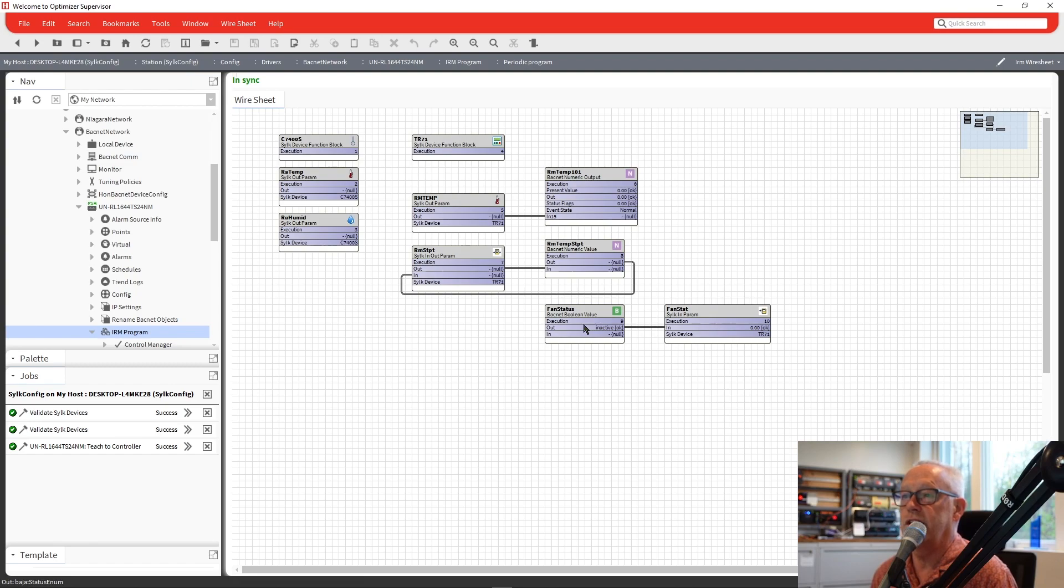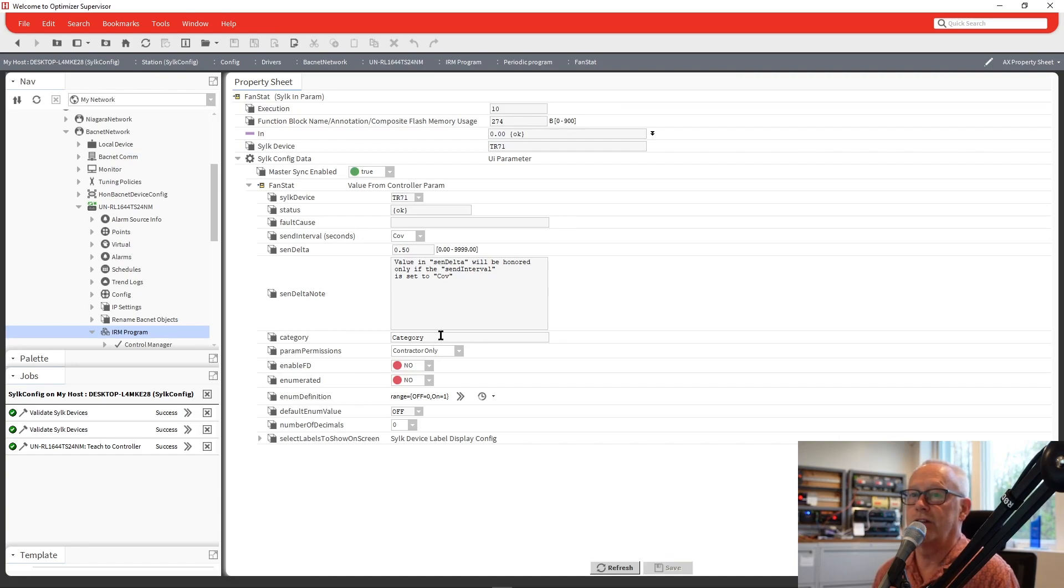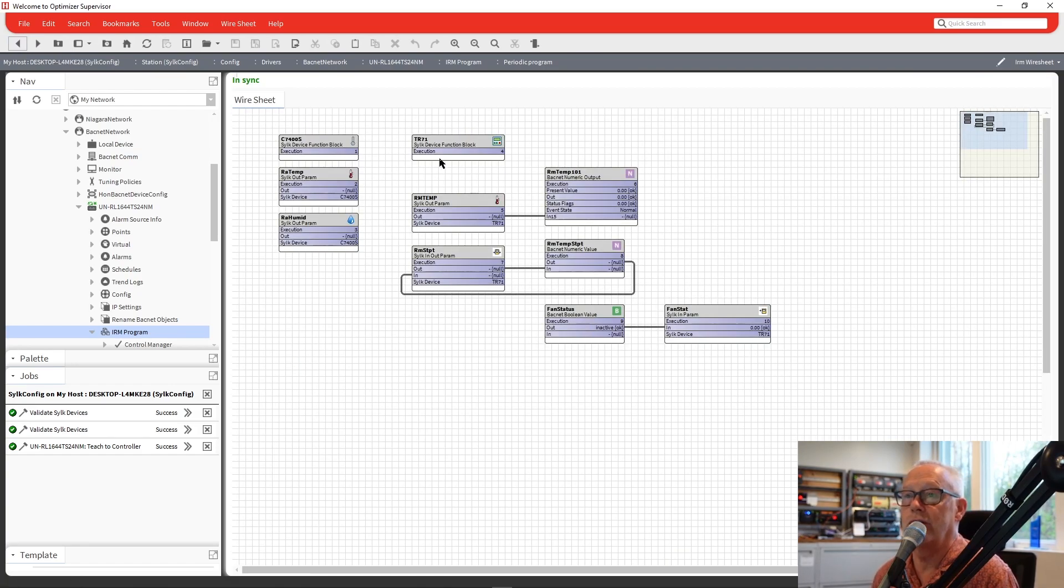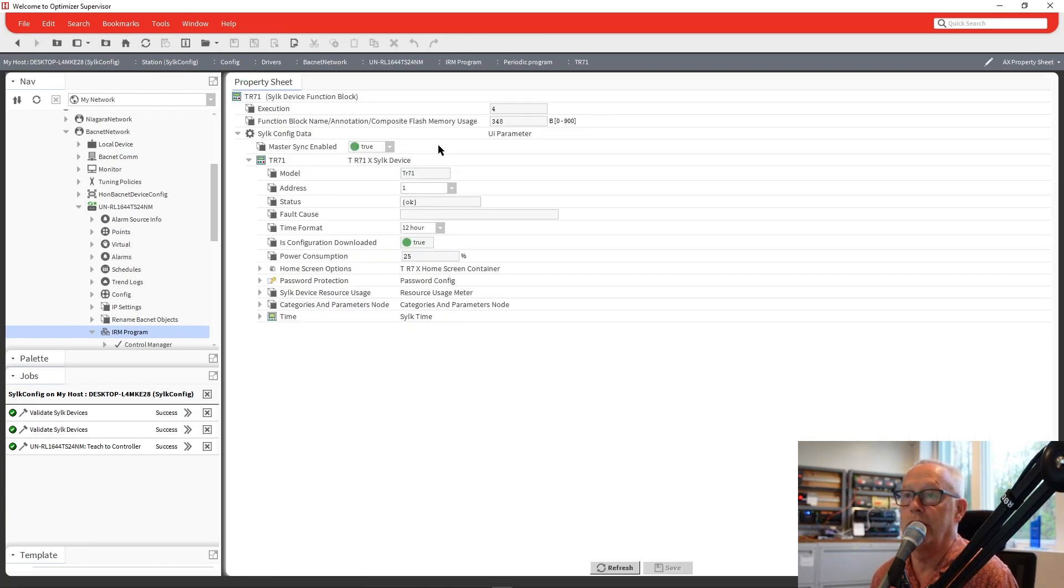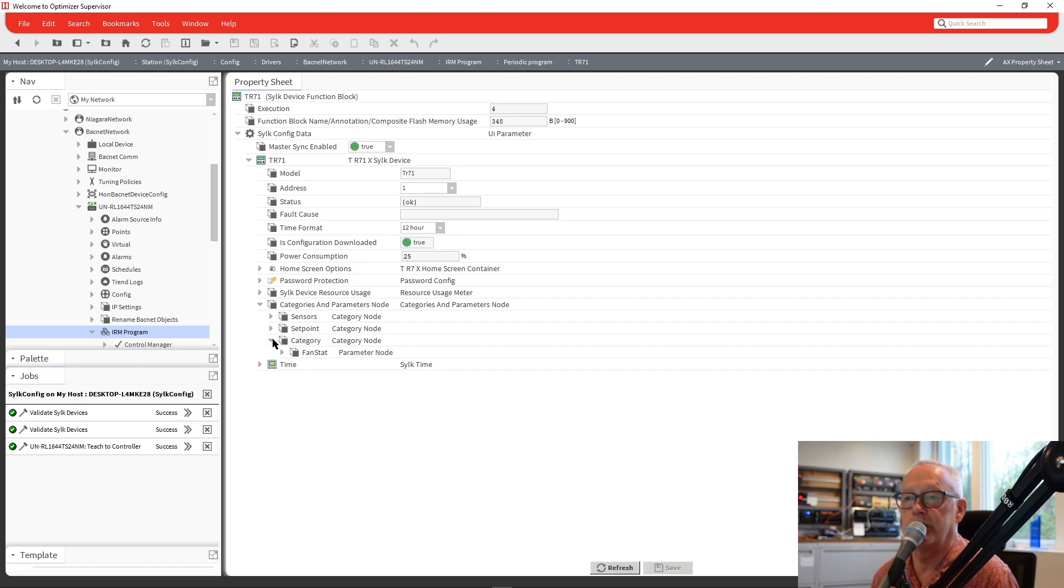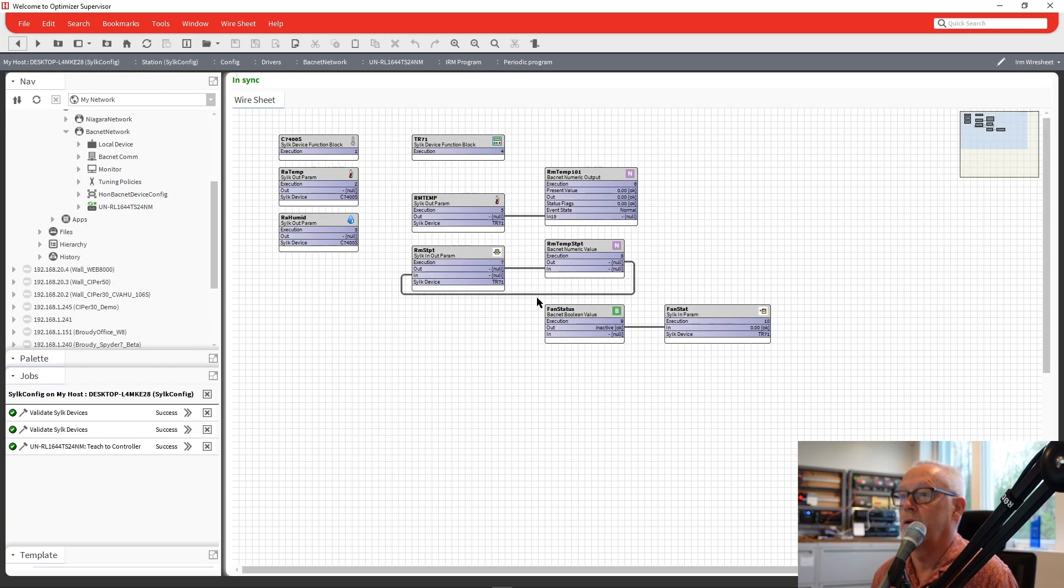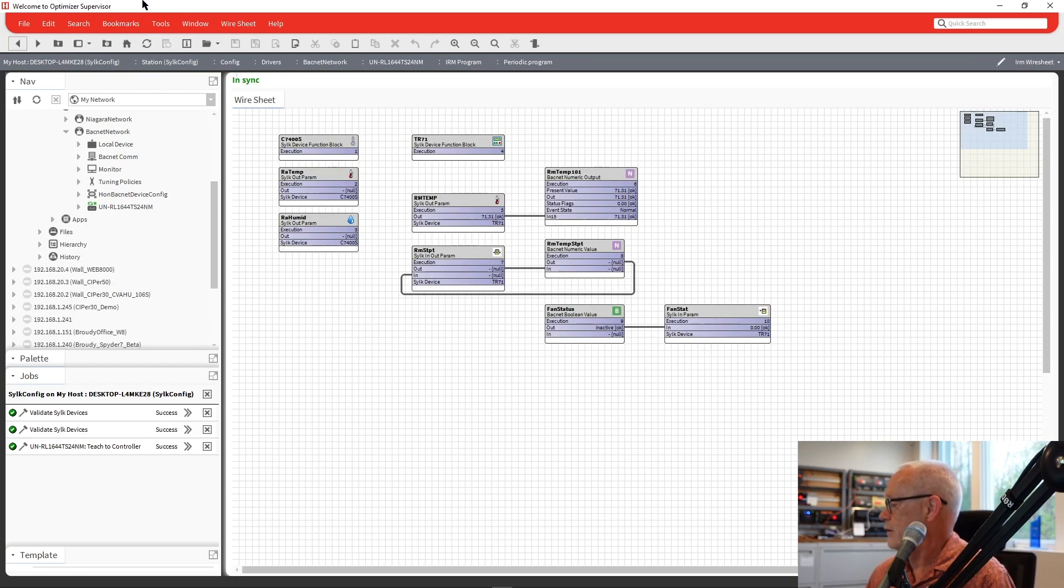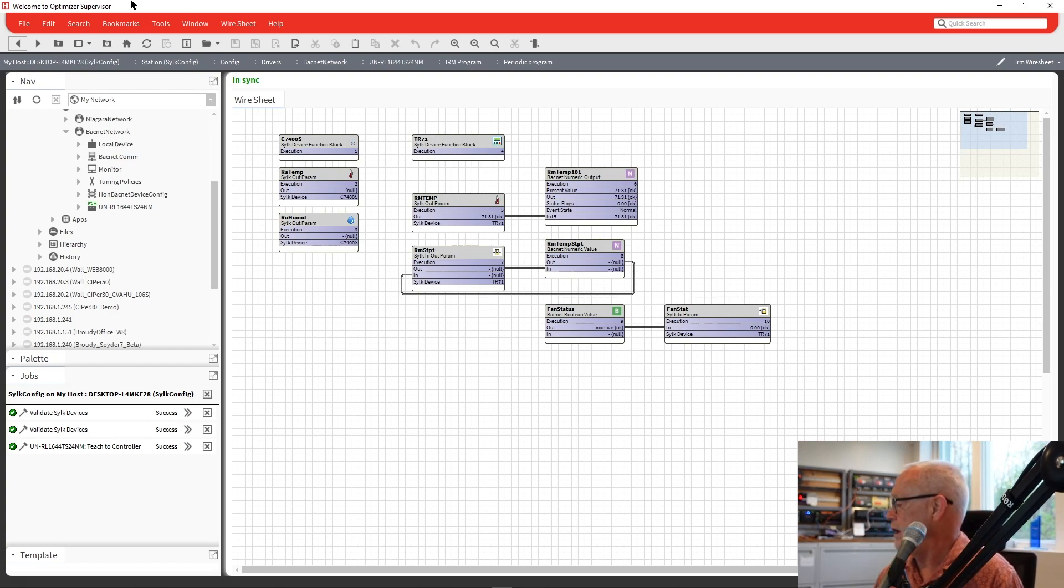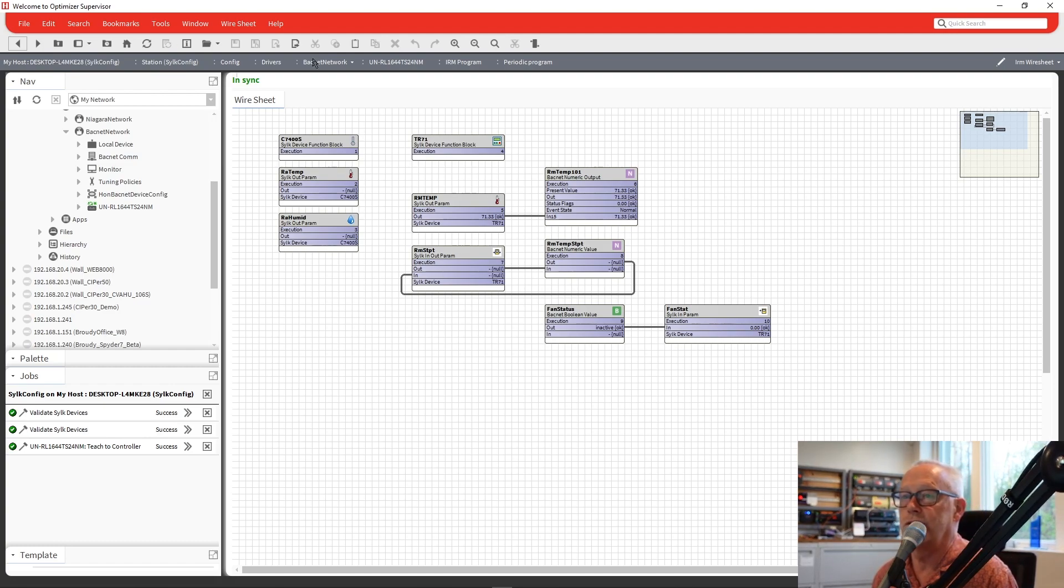And you'll see, I think one thing I did forget was go in here on the categories. I just have it as category, category. So what's that going to do? It will come up here and it would actually make it a category called category, which doesn't really make much sense, but it still created its own category for that. And we have our other ones in there. So now I have on my Xeo, it's there. I can go into my contractor mode and I can go through and go to parameters and I can see my various categories in there and choose the points that I want to see. So that's pretty much how you would set that up.